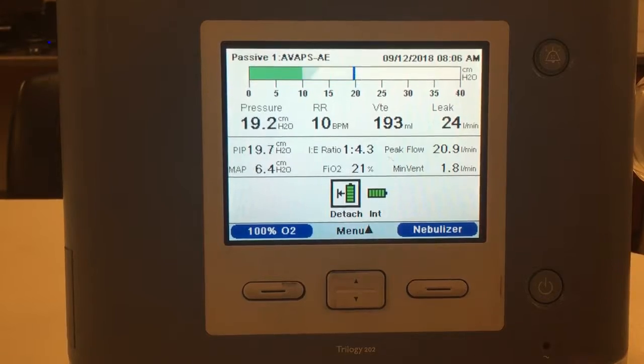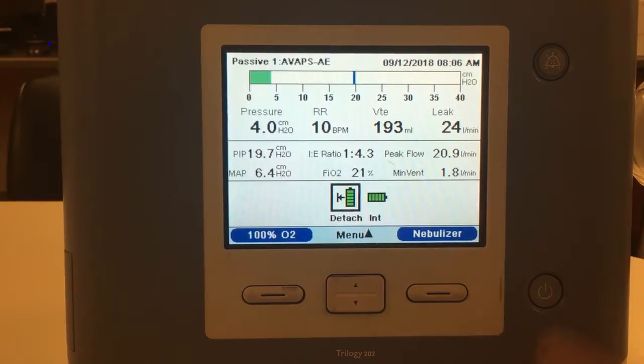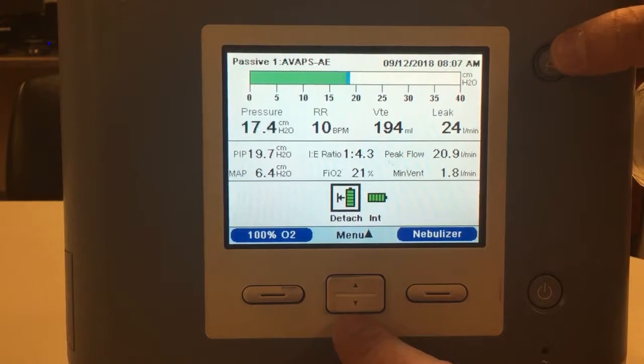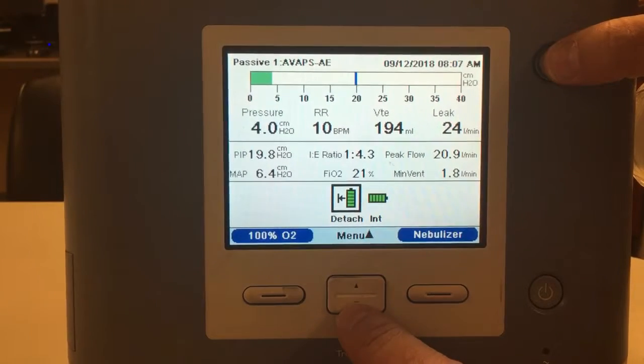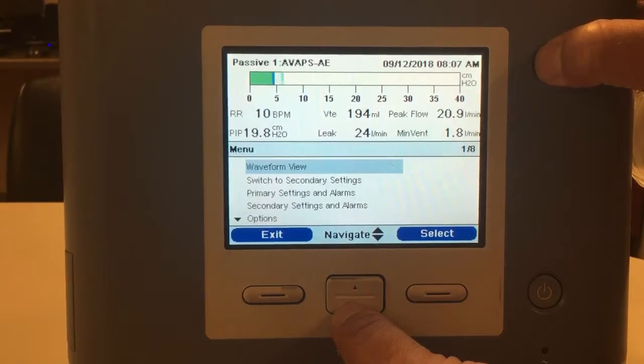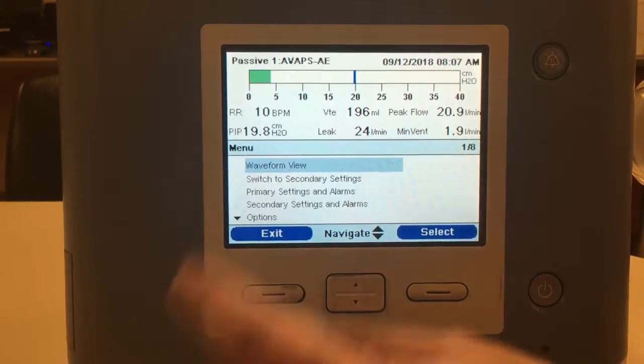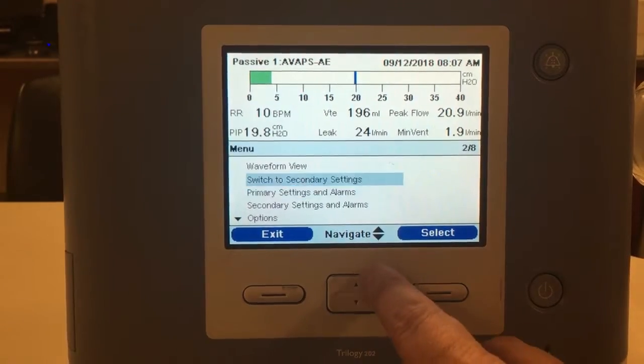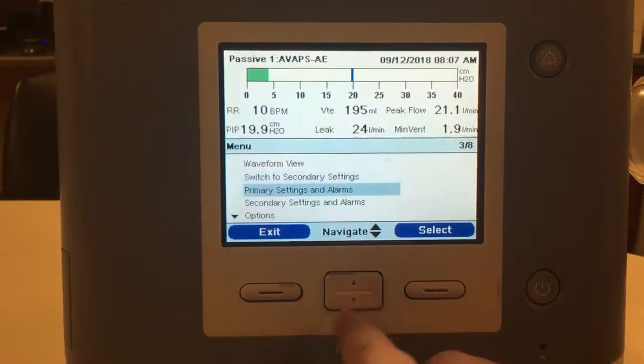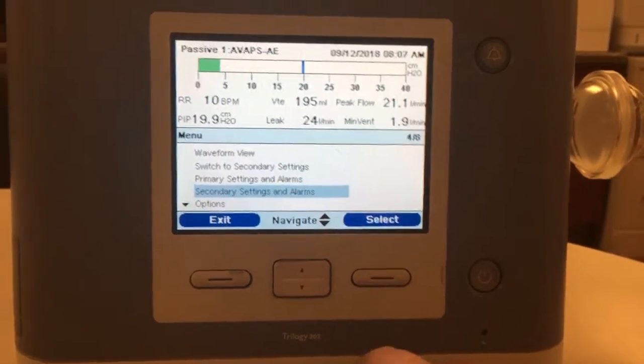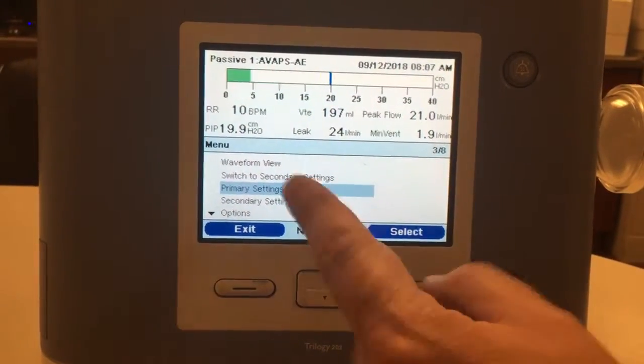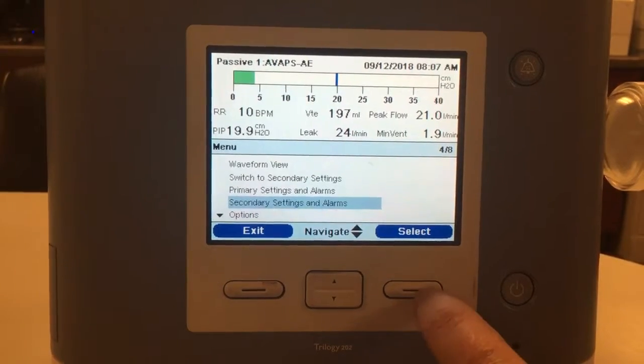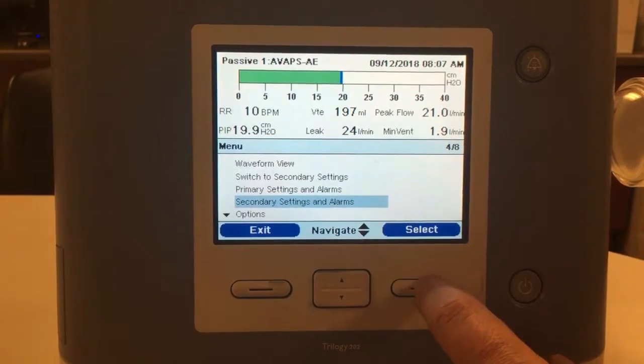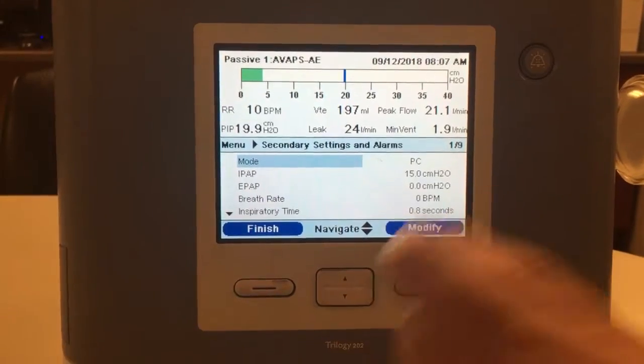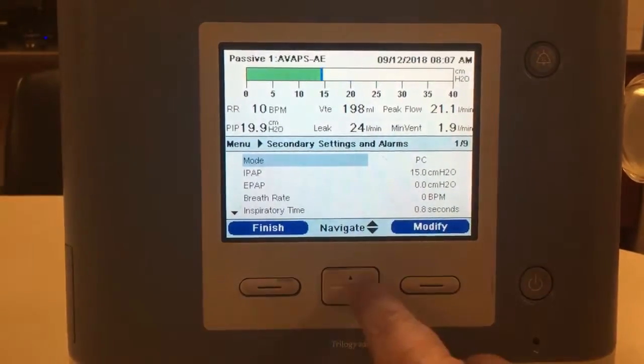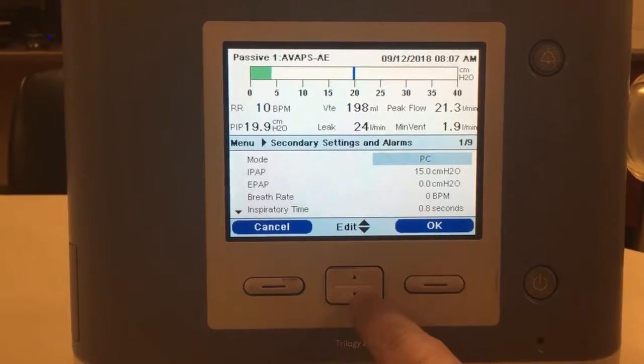And now to get in, you can also access the provider menu with the ventilator on. The same procedure: silence button and the down arrow button. And as you can see now, you're in and you're able to switch to secondary settings, primary settings and alarms, and secondary settings and alarms. For instance, in this case, the patient is on AVAPS AE, but for secondary settings, the physician may want to start weaning the patient. Maybe just a CPAP during the day. What you could do is place this mode into modify.